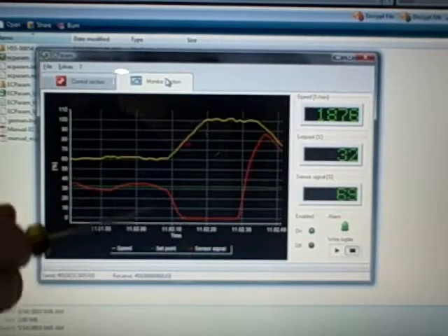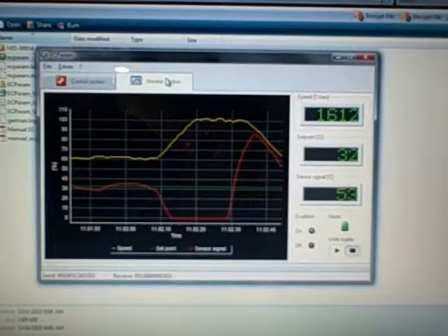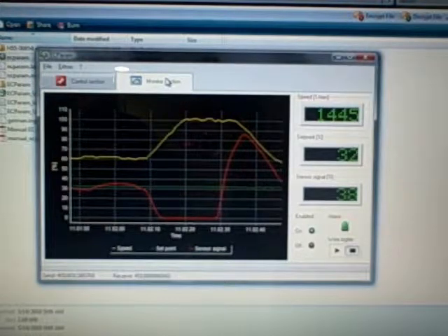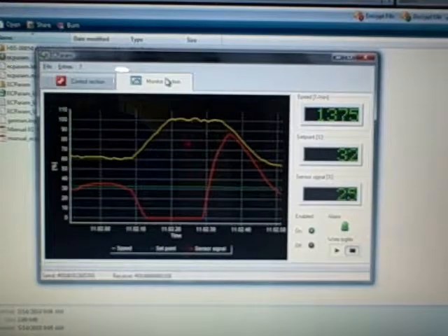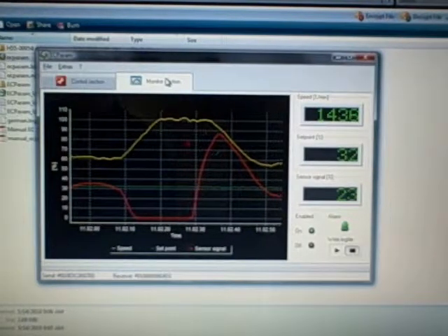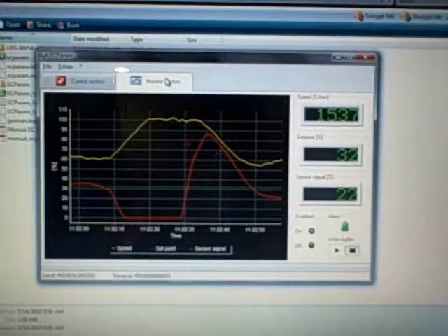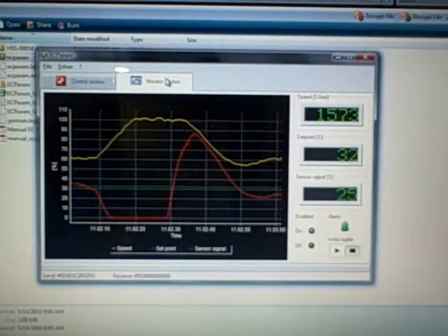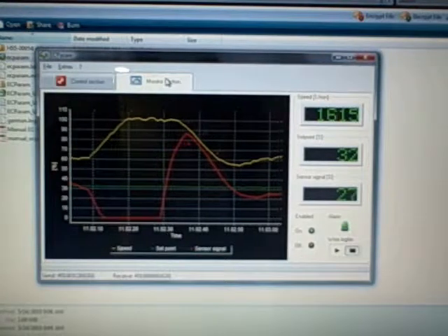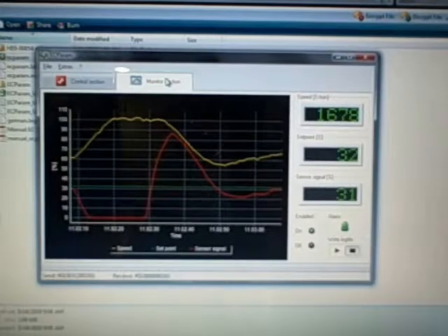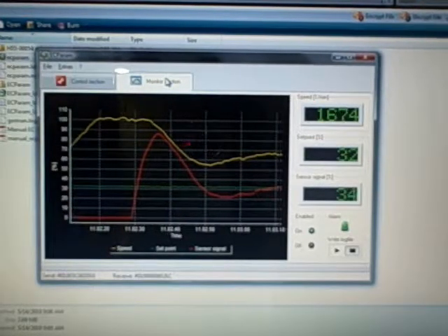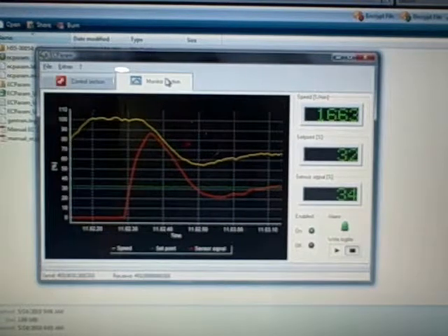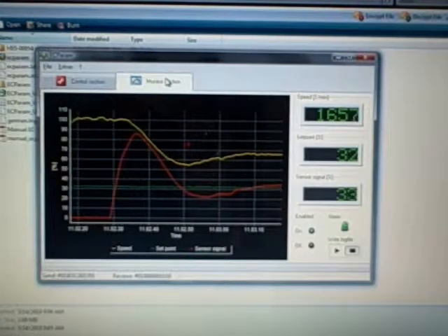You'd find something like this if your filters were completely clogged or your coil was dirty. And you'll notice here as everything starts to balance back out. And what's nice about this is you'll be able to monitor it remotely. So you can have this computer set up in an office somewhere and have an EC fan in a rooftop system or a VAV box. And you'll be able to tell if your filters are ever dirty. So you'll be able to change them in time. You can tell if your coil is dirty.